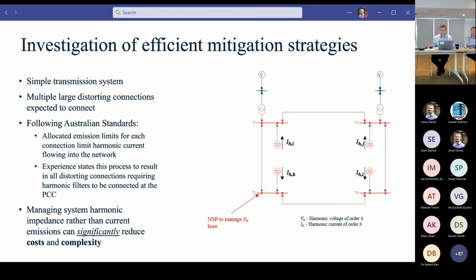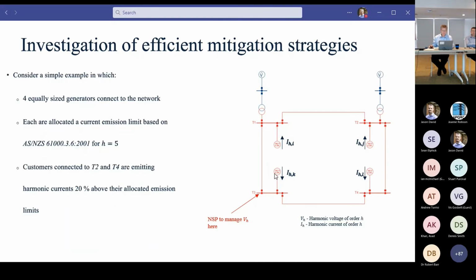And ultimately, we will look at where the voltage distortion is at the point at which the planning levels are expected to be exceeded or to reach initially. So in this example, we've got 4 equally sized generators that are connecting to each of the individual terminals. Each is allocated an emission limit.